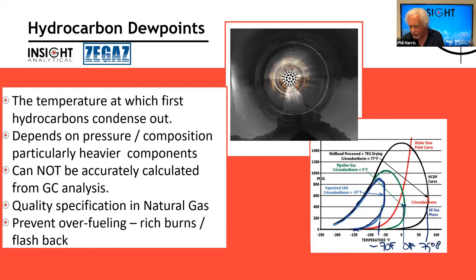And so the important thing here is the hydrocarbon dew point is determined primarily by the existence of heavy hydrocarbons. People will sometimes try to say, well, I've got a GC already, I can just calculate the dew point. Most natural gas GCs only go out to C6 or C9 hydrocarbons, and it's the heavier ones than that that are often leading to where our first dew point is. So if you try to calculate your hydrocarbon dew point from your chromatograph results, you will inevitably not predict the actual dew point. You'll make an assumption that there's not very much heavies there because the GC doesn't see them, and you'll predict a dew point temperature that is lower than your actual one, which means you can potentially run into a hydrocarbon dew point issue.